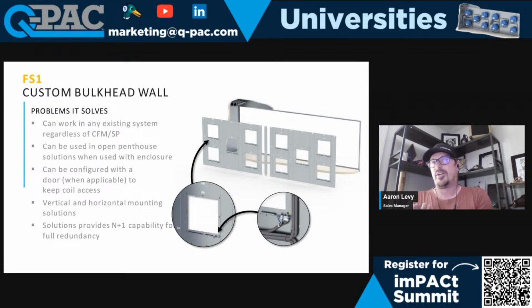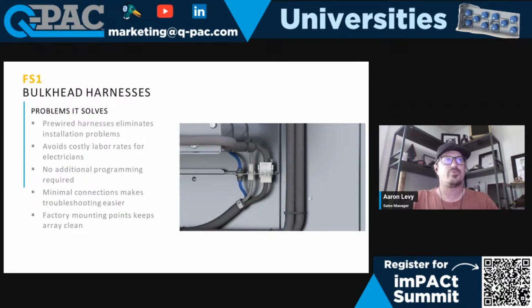We'll ask a lot of questions to make sure we provide a solution that fits the space and works properly. Many solutions provide N+1 right out of the gate. Our selection software gets you close to that already. In many cases there will be changes to your system - when you do a retrofit, there's probably going to be a pressure drop from removing that old double width double inlet blower to a fan array system that's now straight through, with less pressure inside the array by cleaning that up. So you'll see some kind of pressure savings. Sometimes when we're just on the close side of that redundancy number in our submittals, once they balance the system it will actually be fully redundant. So we provide that as well.